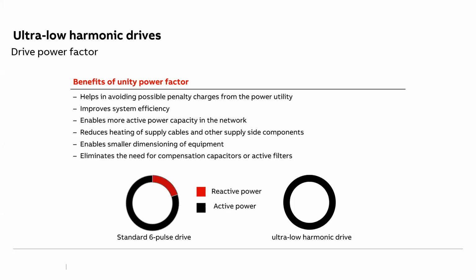So this helps in avoiding other costs like power factor correction devices. By using this, with all the advantages which were there, we can reduce the size of the transformer, we can reduce the cable sizes, we can reduce the sizes of the switchgear and other intermediate circuits which are there. And the overheating issue is taken care of in this.